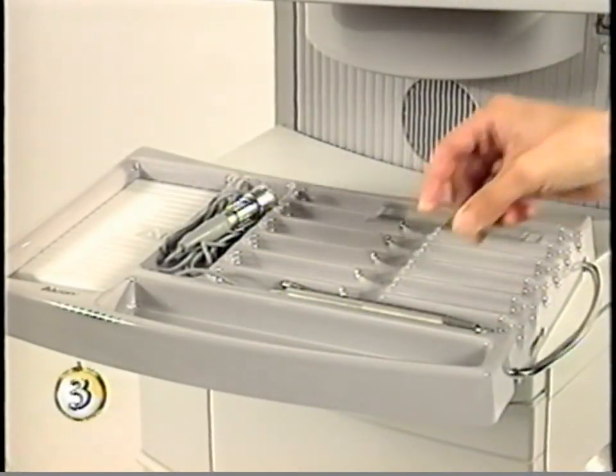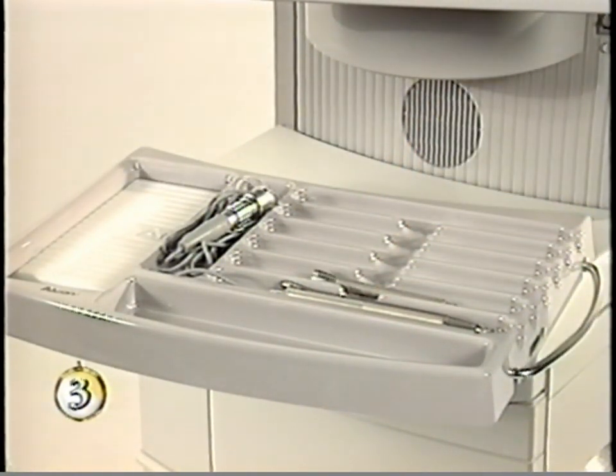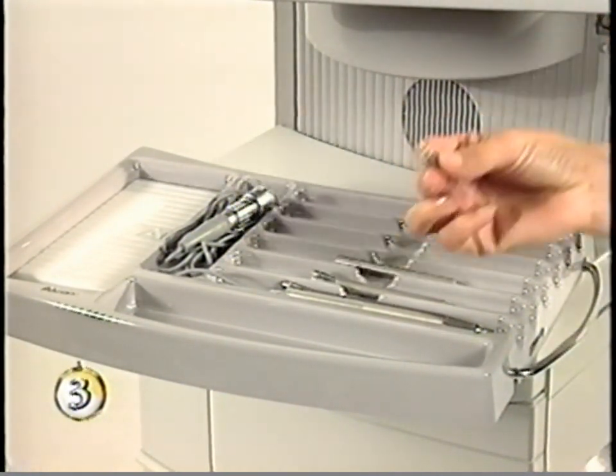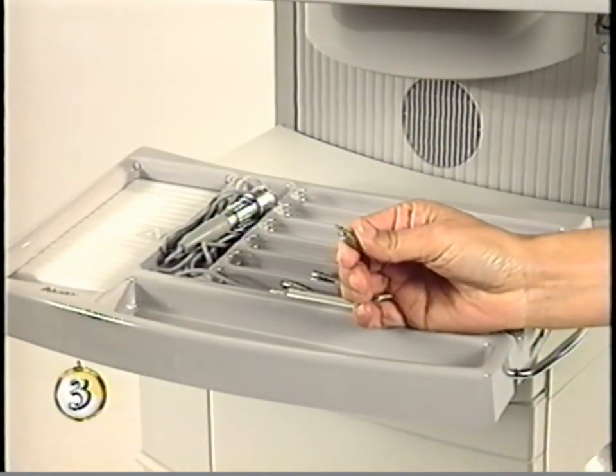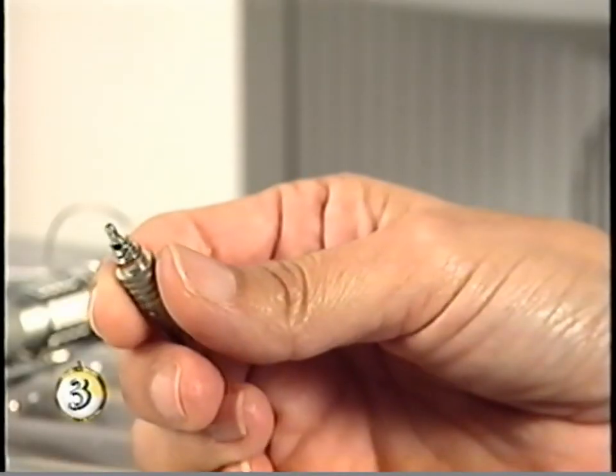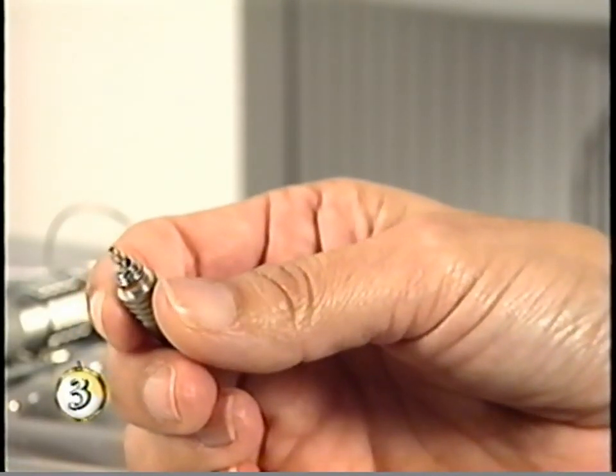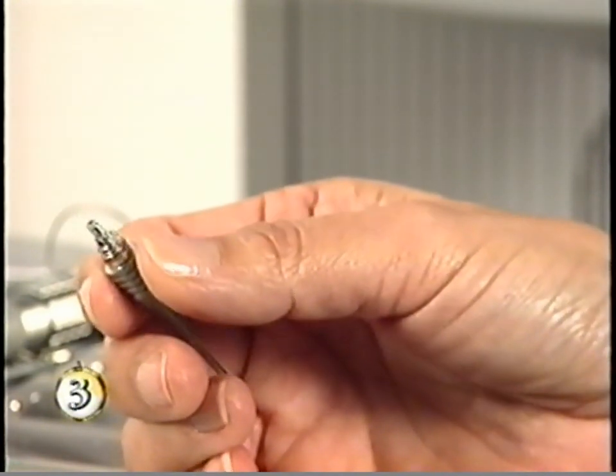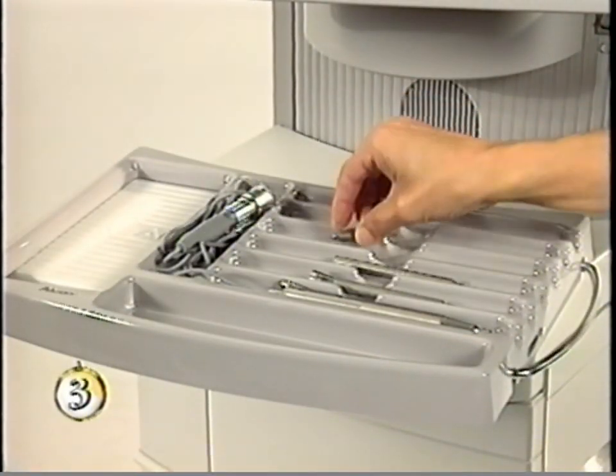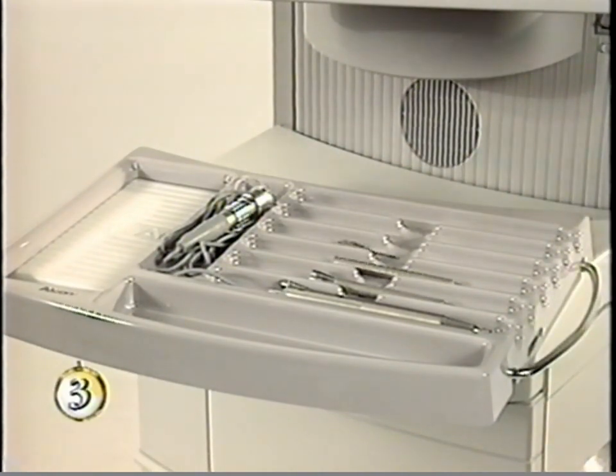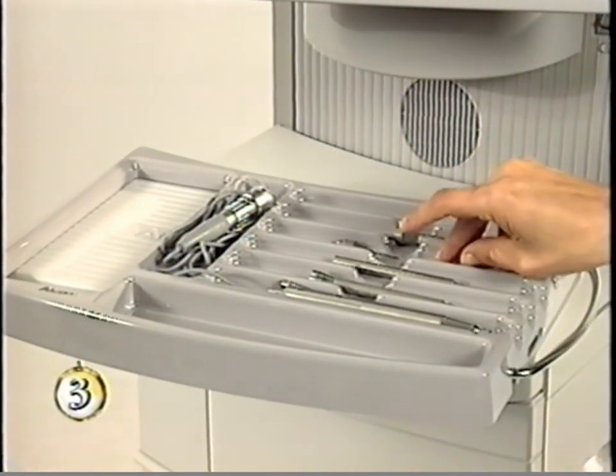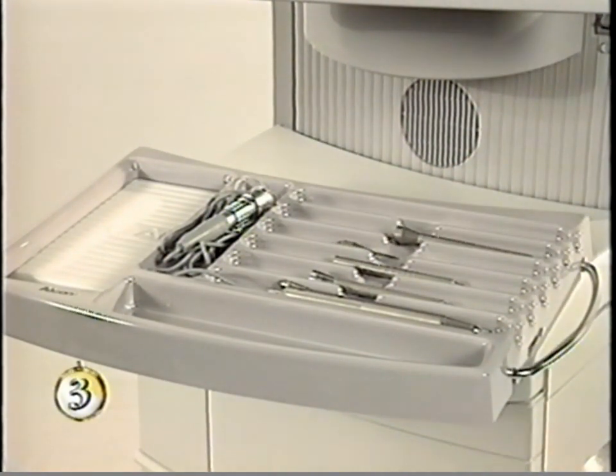The circulator places all items to be sterilized on the instrument tray. Before sterilization, inspect the O-ring at the end of the tip section of the UltraFlow IA handpiece. If damaged, it must be replaced. To reduce wear on the O-ring tool, do not sterilize it each time the UltraFlow handpiece is sterilized. Instead, sterilize it wrapped so it can be stored. The troubleshooting section of the operator's manual explains O-ring replacement.